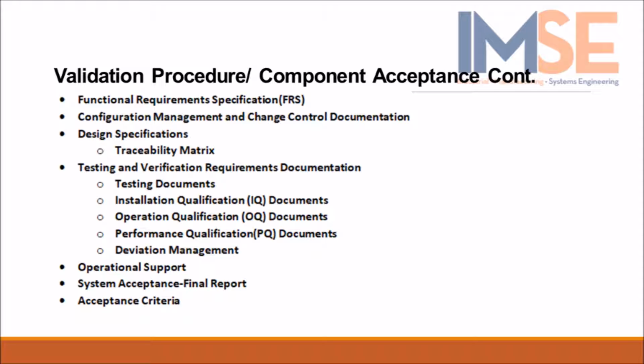Design specifications may include the traceability matrix. Traceability matrix is the traceability of critical parameters and data through the design process to the final testing stage will be maintained using a matrix. This matrix shall detail all critical equipment and software parameters and link them to their individual test cases and the document in which they appear. The requirements traceability matrix shall be maintained under change control for the life of the equipment.